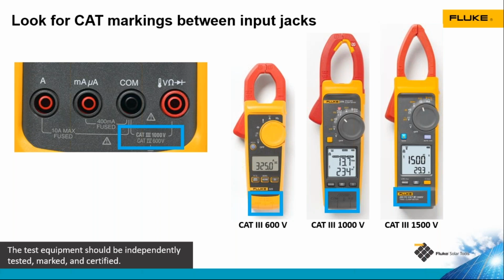The one thing that I like to point out is that as the voltage rating goes up, the size of the tool goes up as well. And that's because there's extra space inside the tool for safety. With higher voltages, there's a potential for higher transient voltage spikes. So we want to make sure that there's enough space in that tool to absorb that transient voltage without causing a hazard to the technician.